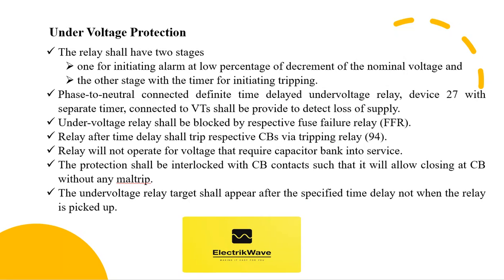The under voltage protection is to be provided in the scheme of protection with the fundamental voltage sensor with a timer with adjustable time settings. The relay shall have two stages: one for initiating alarm at a low percentage of decrement of the nominal voltage, and the other stage with the timer for initiating tripping. A phase-to-neutral connected definite time delayed under voltage relay, device 27 with separate timer connected to voltage transformers, shall be provided to detect loss of supply. The under voltage relay shall be blocked by the respective fuse failure relay.